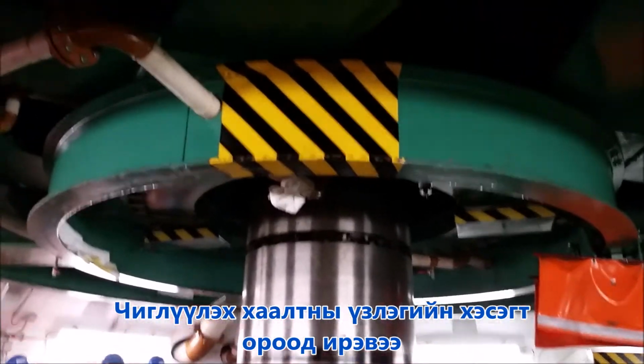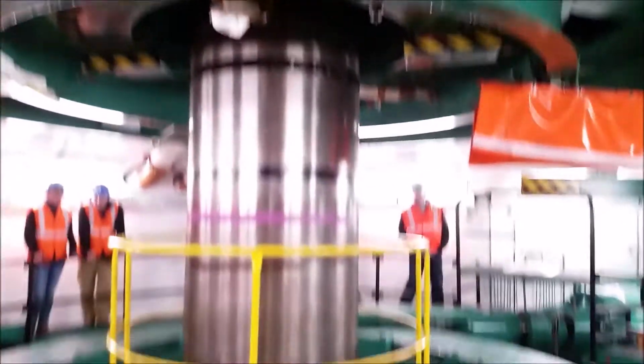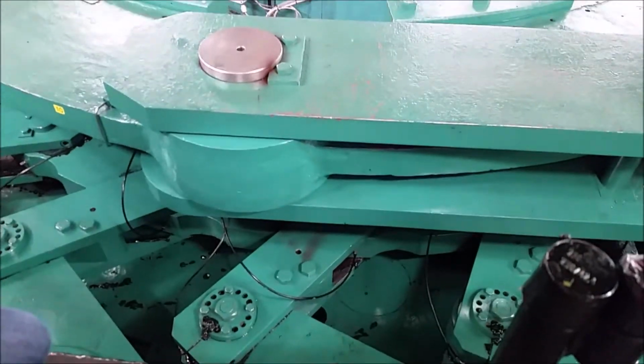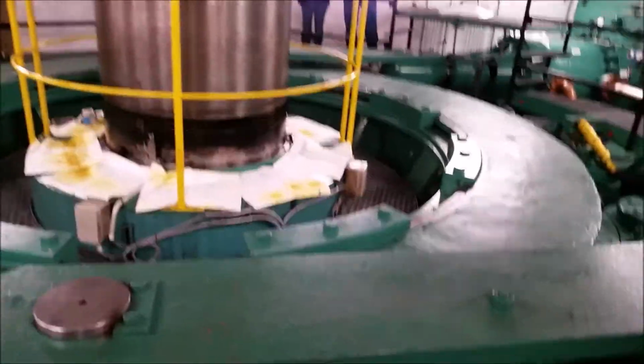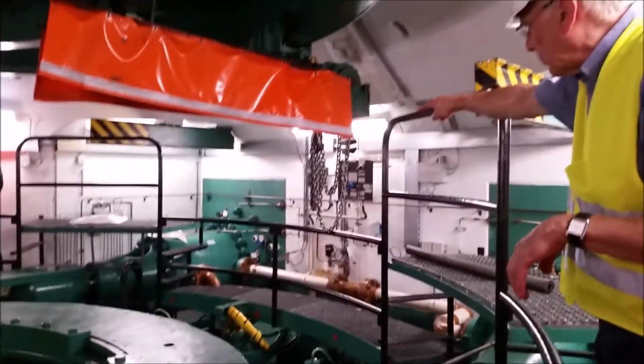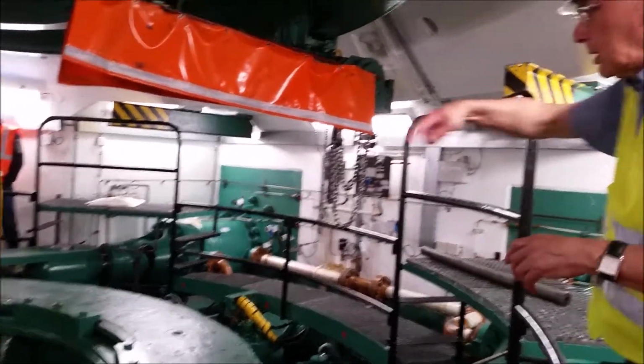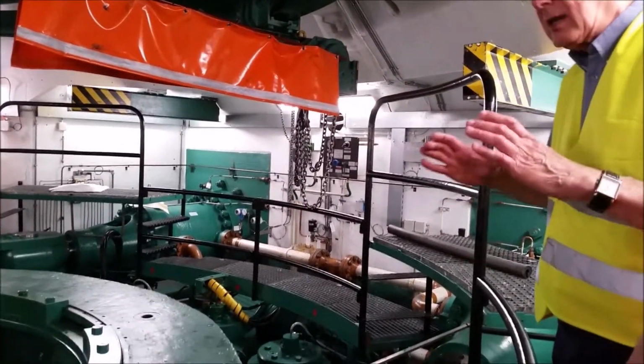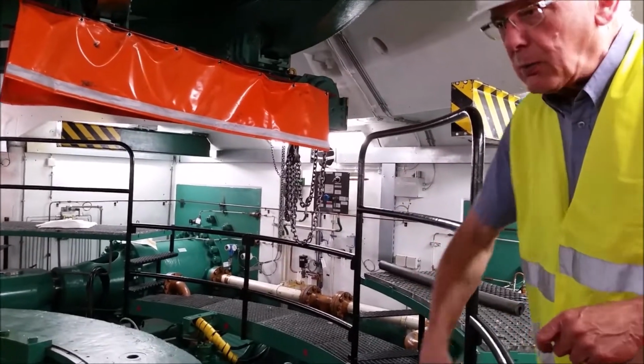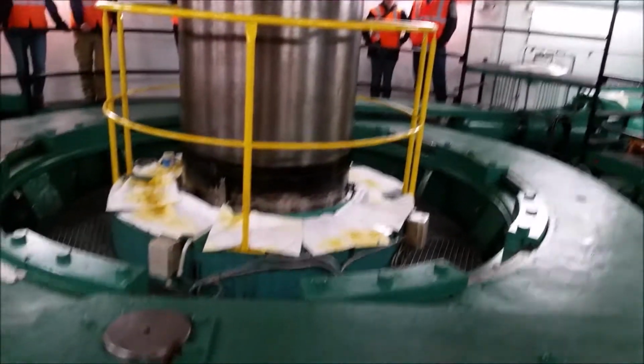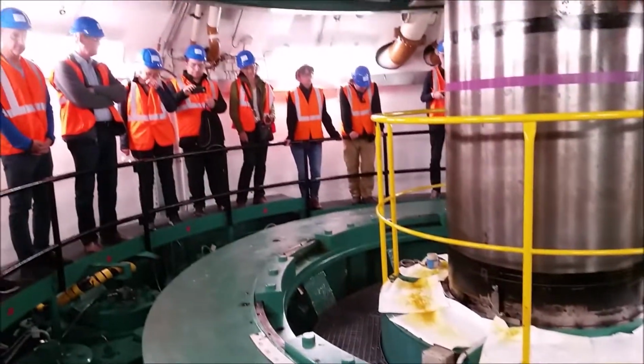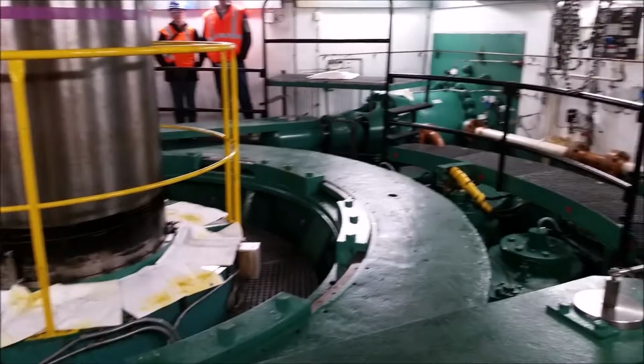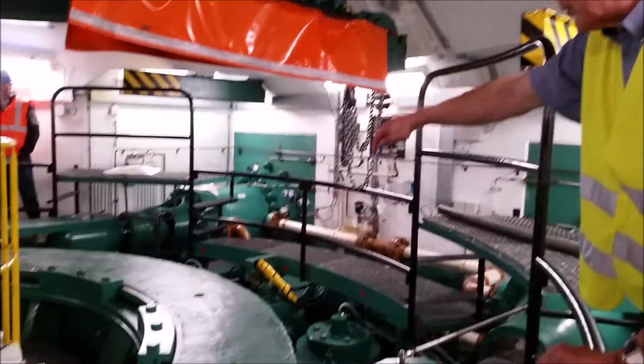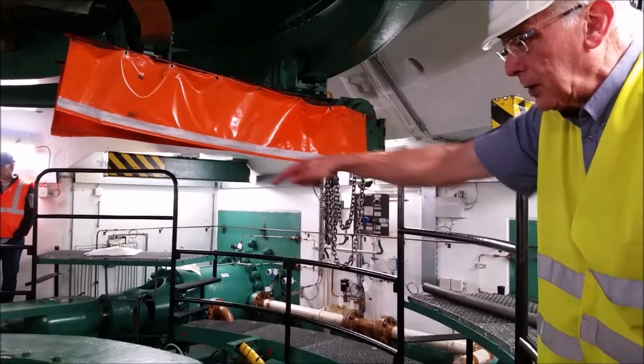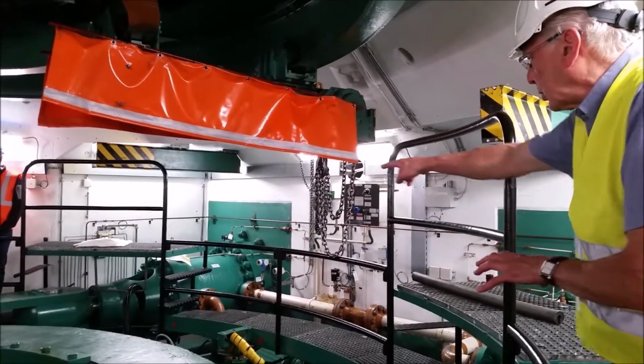On the top here we have the electric part with the generator. We are walking now just above the paddle wheel we saw outside. The water is coming from the radial side, not the axial side, and in the spiral casing built around the paddle wheel we have what we call direction valves, which are moved by this ring. This is what we call the control ring. The control ring is moved by two servo motors.